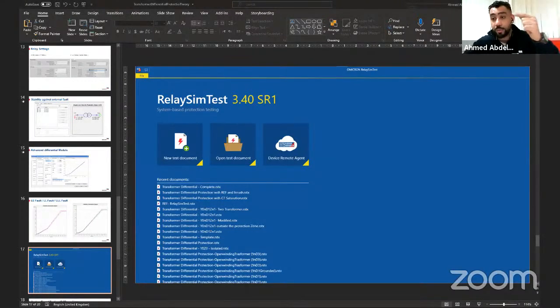What does it mean? Do you remember that when we say I have a fault, I have a node here, and this current is going to each other, and ideally we said this current equals this current. So if this and this are going to the same point, it means both of them are equal. So if you sum both of them vectorially and scalar, you will see that it is I plus I. This is I differential, so it will be 2I. And the other one, which is scalar, to represent the bias current, this will be I plus I, so it will be 2I. So the differential current will be 2I, the bias current will be 2I. And if you draw a characteristic, it will be a line passing through the origin with a slope of 1, which is tan delta of 45 degrees.